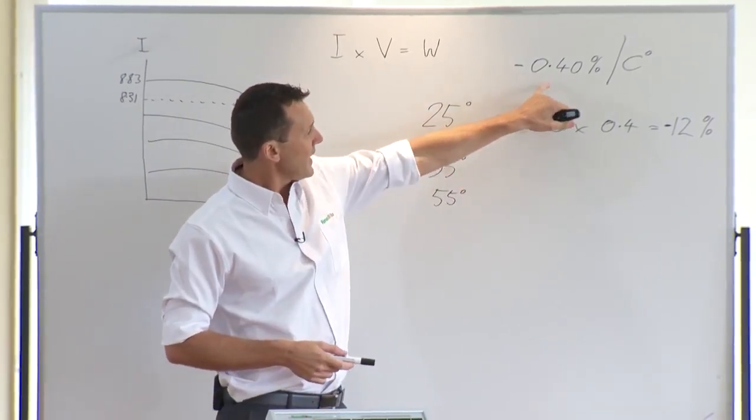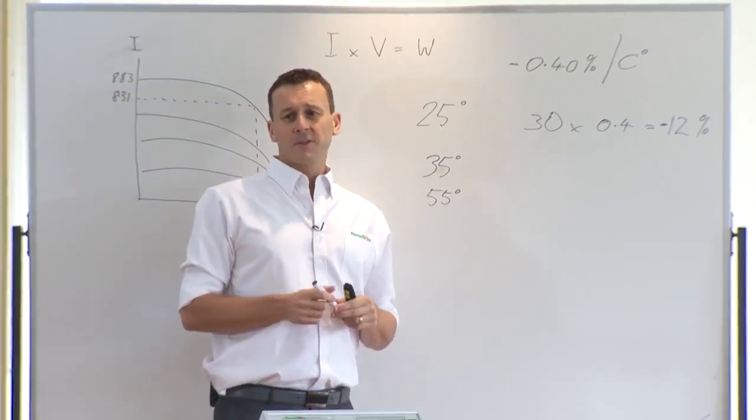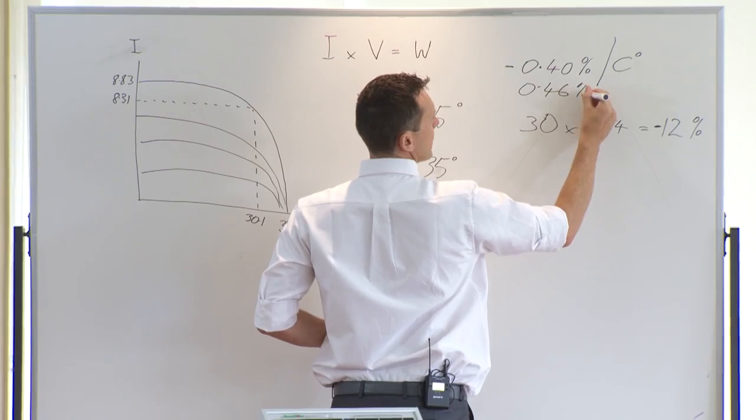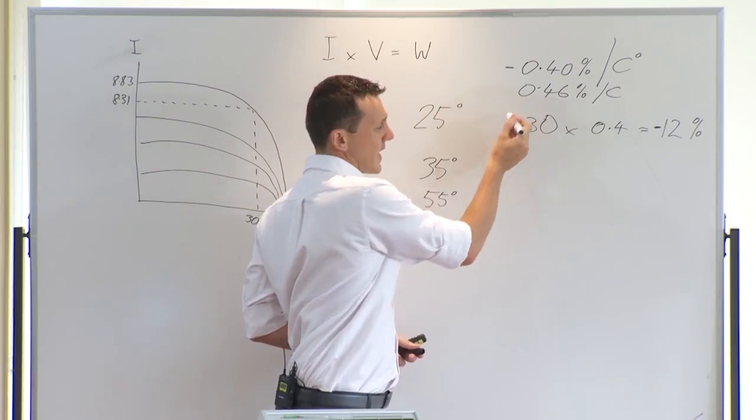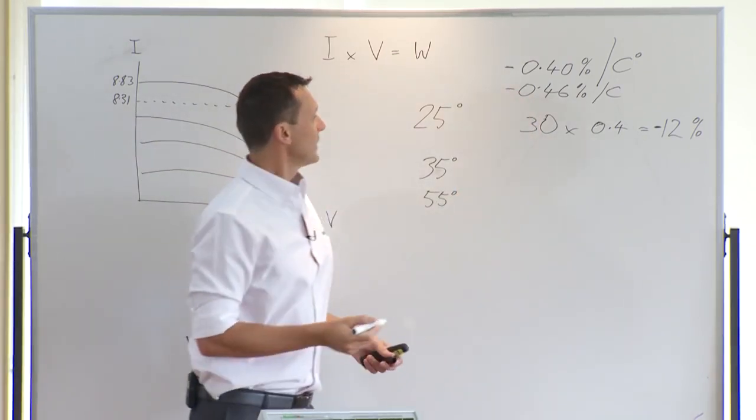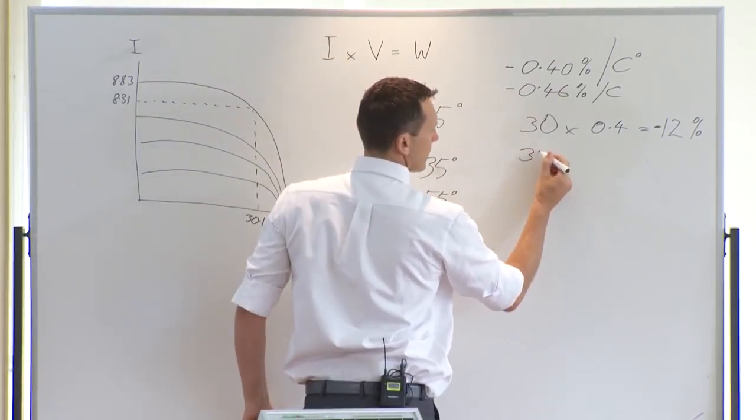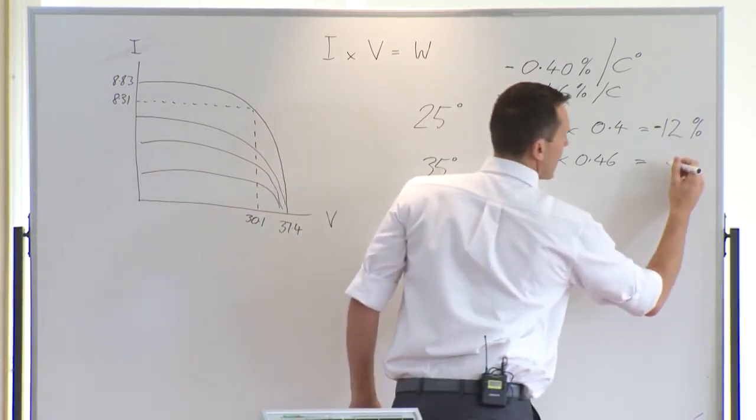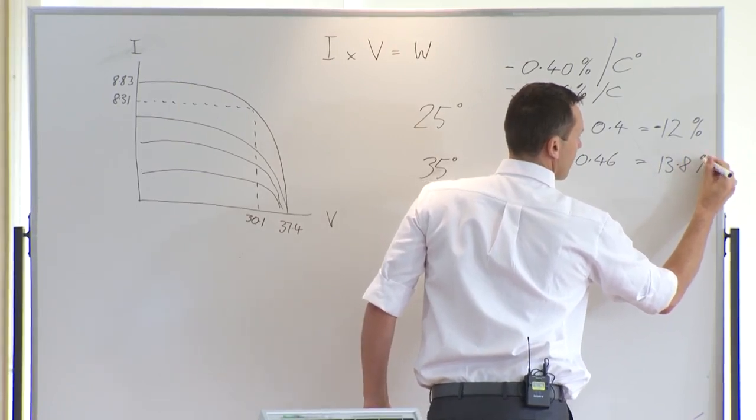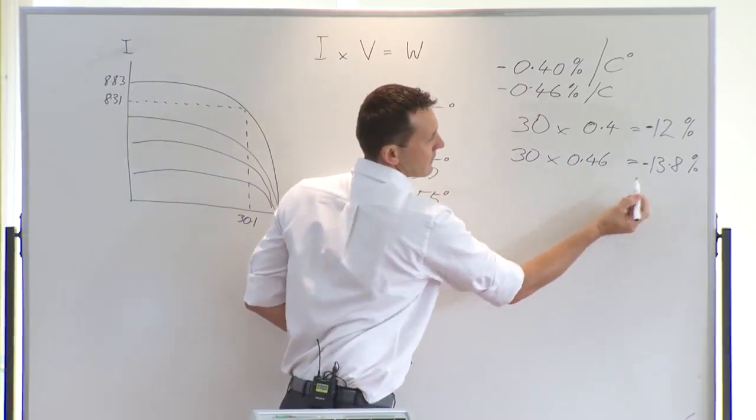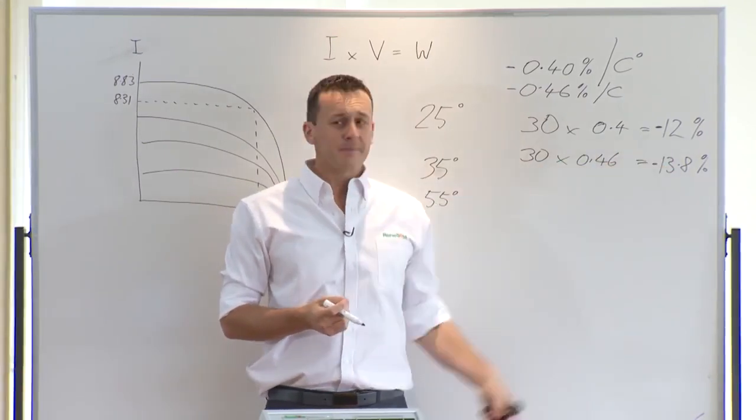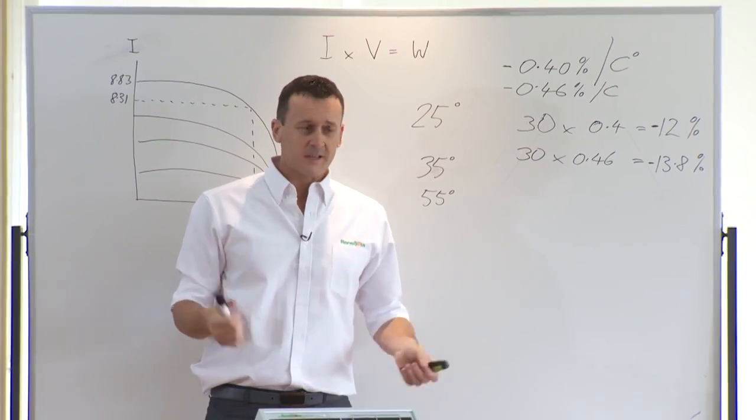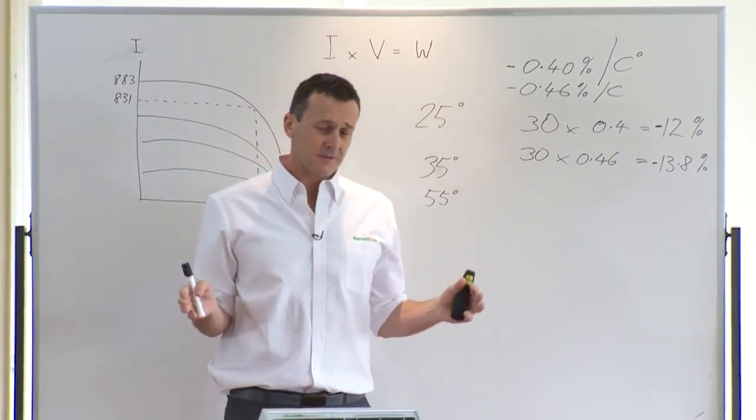So if we do a comparison of, say, another brand of module that may have a temperature coefficient of 0.46% per degree Celsius, and again that's not uncommon, that's fairly standard for a monocrystalline panel on the market. Under these same conditions, if we do that 30 degree temperature change times 0.46, 13.8. So as you can see, that loss of that particular module under the same conditions is 1.8% more than this module with this temperature coefficient. So that 1.8% over a lot of hot days, over a lot of years, will mean a significant difference in your total yield for the system performance.